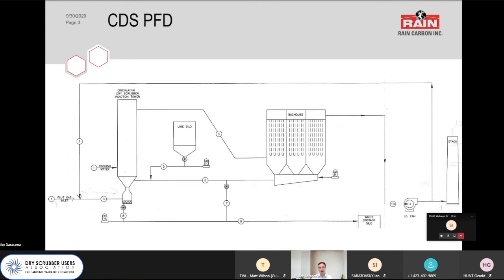And we see that as our acid dew point coming into the reaction tower is probably around 280 F. The temperature leaving the reaction tower is 220 F, but we don't see any corrosion. So to me, that means the majority of the SO2 is being removed in the reaction tower, and maybe a small amount is being removed in the baghouse as well.